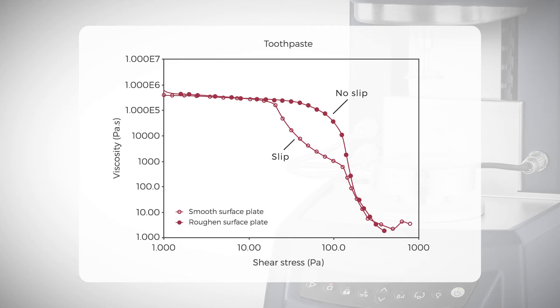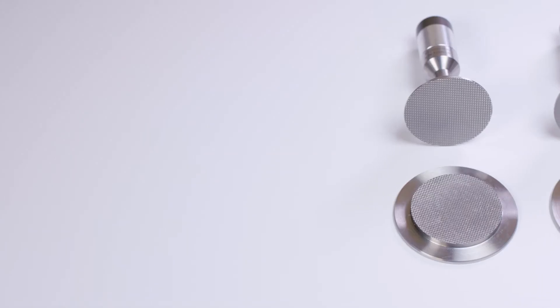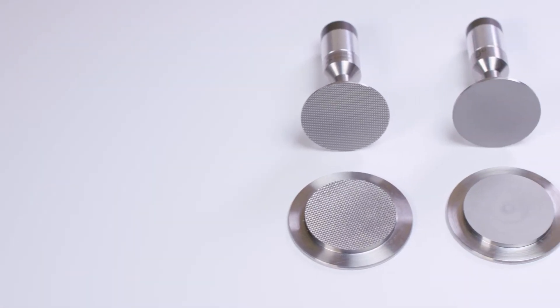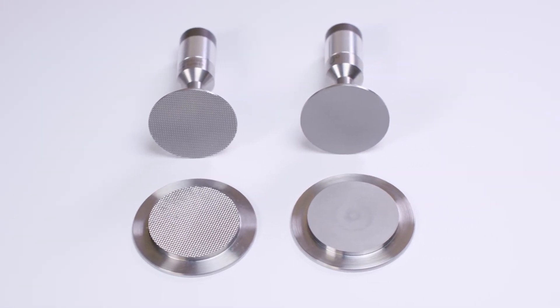In order to avoid slippage during viscosity testing, TA Instruments provides to our users some rough surface parallel plate geometries.